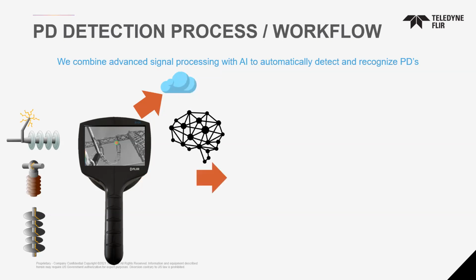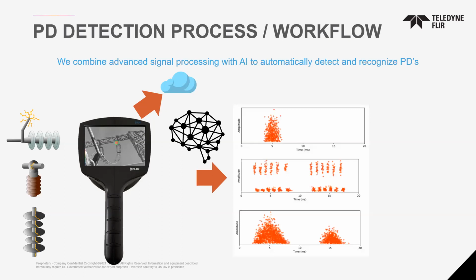Once you're connected to the internet, that image, on our software that is free to use, is processed, right? We have this artificial intelligence, and that image goes under processing to really understand and identify what it is. You'll have one of 3 things: discharge to air, discharge to the component, or discharge internally. If you have discharge internally, this is the one that indicates the biggest problem. Discharge to air, there is going to be a certain amount of discharge, and it does not necessarily mean that anything is wrong, but maybe just something to note.